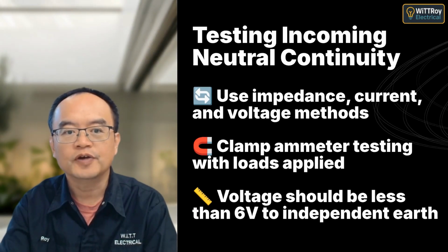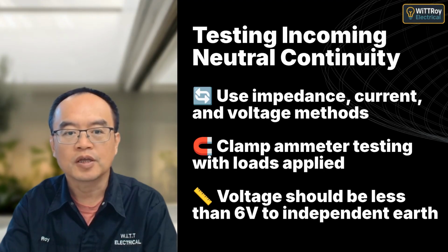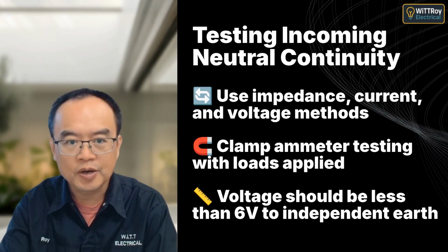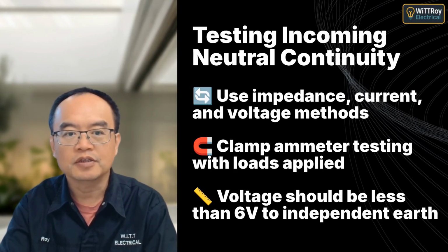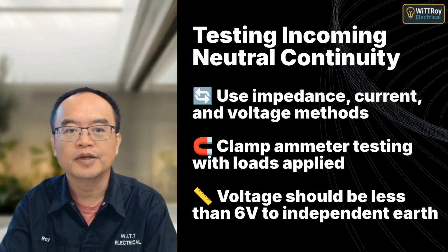Neutral integrity is verified using impedance, voltage, or current methods. Under load, clamp current in actives and neutral should match. Voltage between neutral and earth must be under 6V.